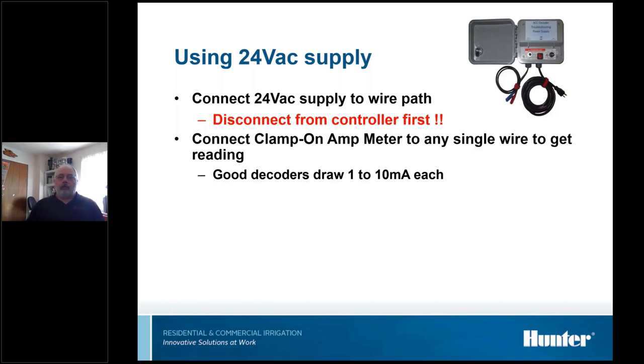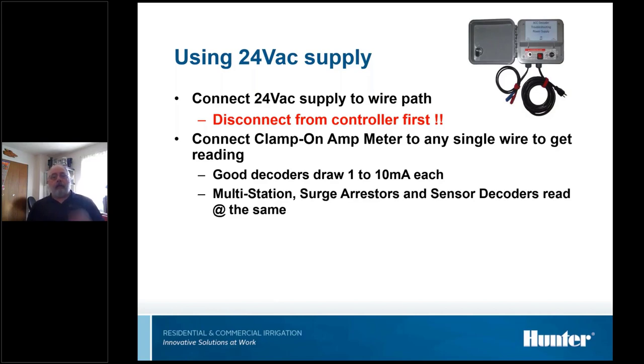And then if you put the solenoid in line with the transformer, then readings drop tremendously. There's quite a bit of variation as to what they might be, but they will all draw some. They'll draw at least a milliamp, even the good ones. If they draw more than 10 milliamps, you might as well replace them. They're bad. And all the stuff reads about the same, whether they're single station, multi-station, or sensor decoders, they all draw about the same amount of current.